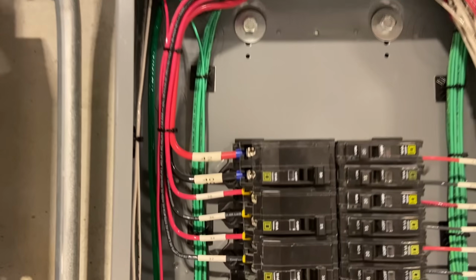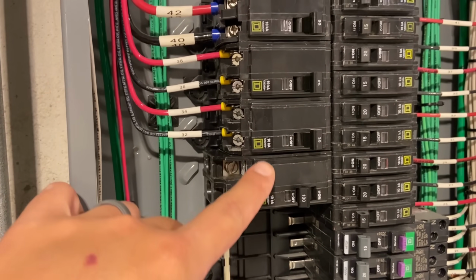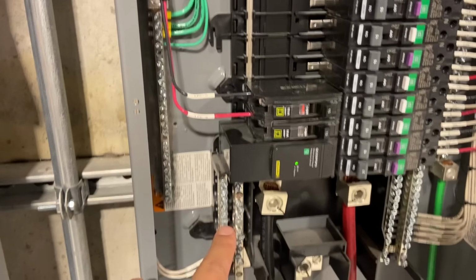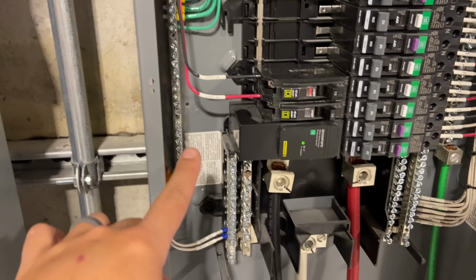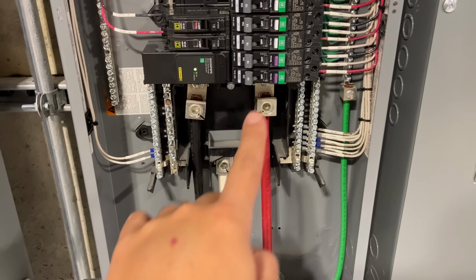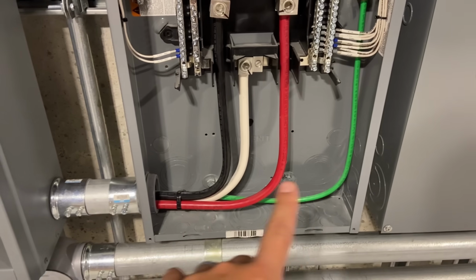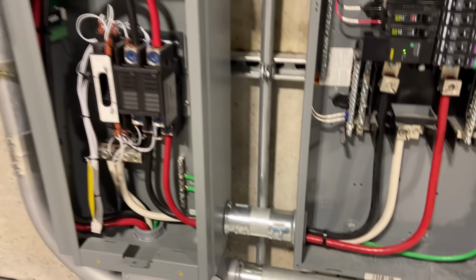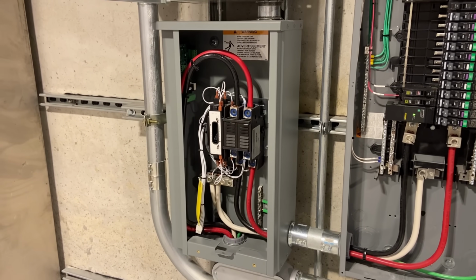Down one of these 1-inch pipes and backfeed into our 100 amp breaker. And then obviously our neutral will go to our neutral bar down there, and our ground to our ground bar. The grounds and neutrals are separated in this because it is a sub panel. That gives us plenty of room to get rid of all these larger wires, the piping, everything that needs to be removed.